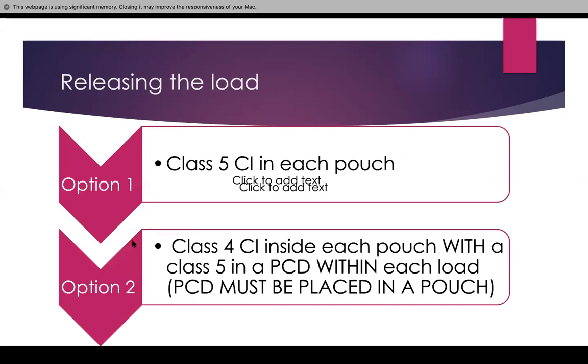Recording load numbers on patient progress notes creates much less hassle for us. For releasing the load, you can have a class 5 in each pouch or you can have a class 4 inside each pouch. I'm going to show you what a class 4 looks like, and then a class 5 in a PCD within each load. The PCD must be placed in a pouch too.